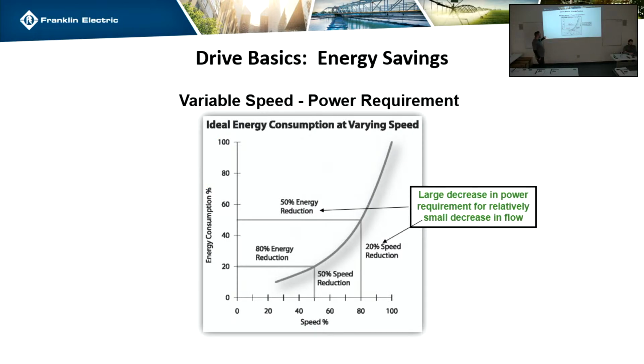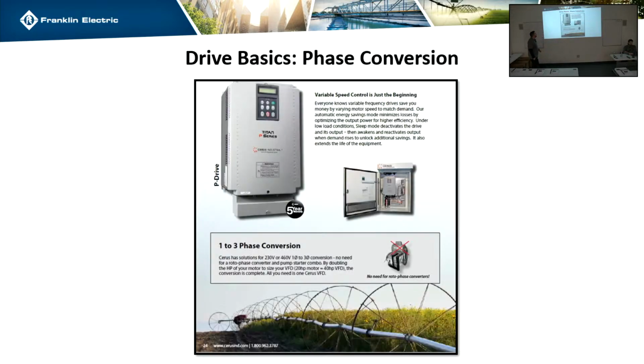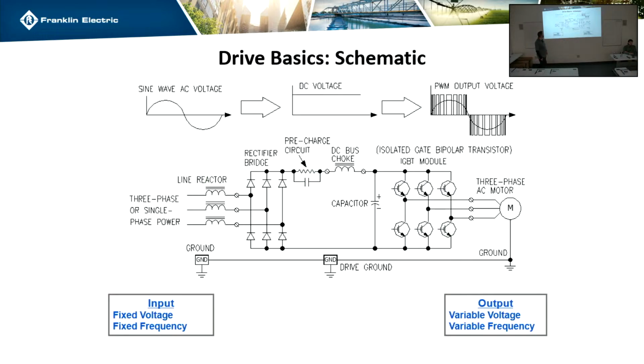So this is just a graph explaining what VFDs do and why you would want a VFD over an across the line starter. You can control the speed, and your energy is greatly reduced. It's far more efficient. All the drives can do phase conversion. If you have a panel, it has to be set up for single or three phase. You can't just switch it to single phase in the field. But if you have just the drive, all the drives will do the phase conversion. I need to update that. That's the old P drive.